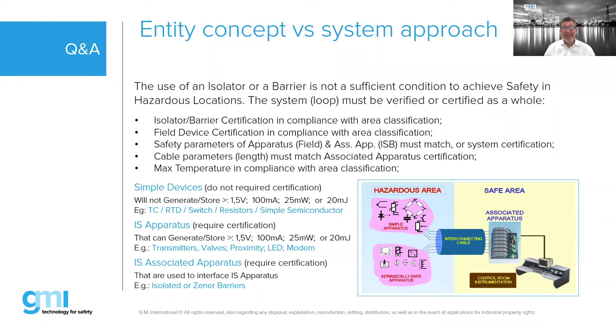With the entity concept, each device is given a set of parameters that must match. The associated apparatus — the barrier — has parameters including: Um (maximum allowed voltage on the safe area circuit), maximum open circuit voltage, short circuit current, maximum power the barrier can transfer, and the maximum capacitance and inductance it can handle. The field device also has its own set of parameters: maximum voltage, current, and power it can accept while remaining safe, plus maximum internal capacitance and inductance. The cable also has parameters because cables themselves can become energy storing devices with capacitance and inductance along their length.